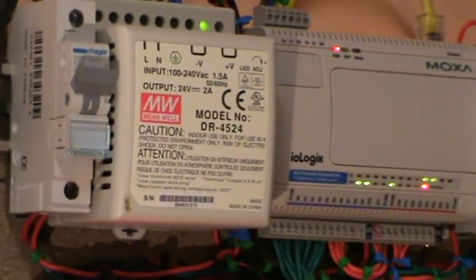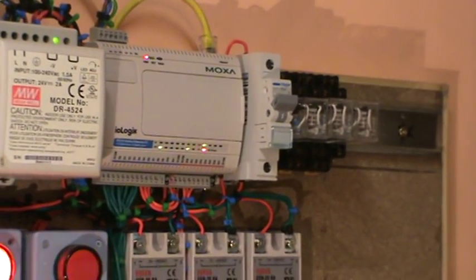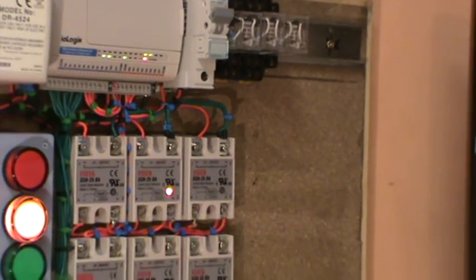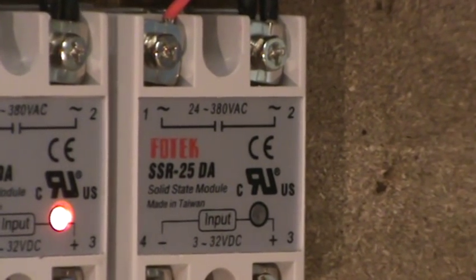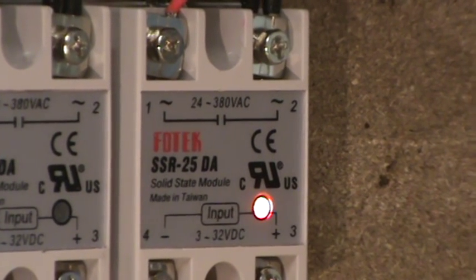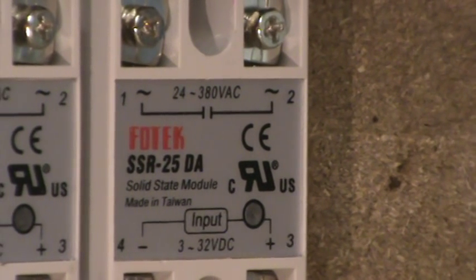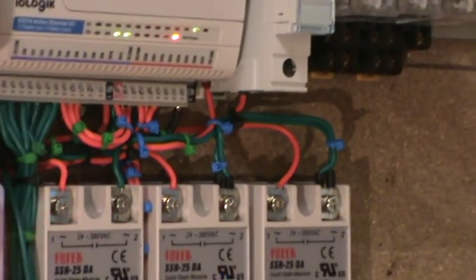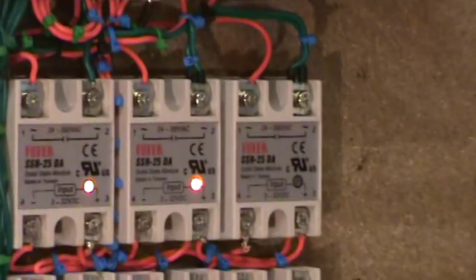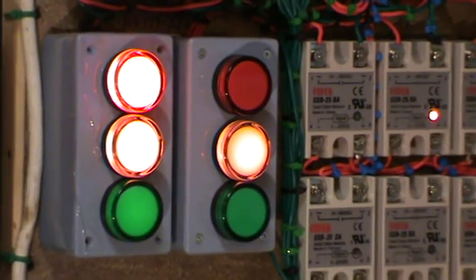The device mounts on a DIN rail along with the power supply, which is very handy — that's a 24-volt power supply. I'm also using relays; these particular ones are bought from eBay and are solid-state relays. They handle 24 volts to 380 volts AC output and accept 3 volts to 32 volts DC input, which works very well with the ioLogik controllers.